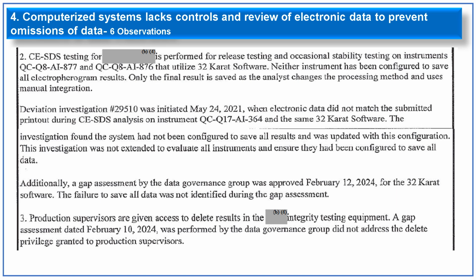The second observation under the fourth 483 states that CESDS testing is performed for release testing and stability testing on two specific instruments that use some 32 Karat software. Neither of these instruments has been configured to save the electronic results. Only the final result is saved, as the analyst changes the processing method and uses manual integration.